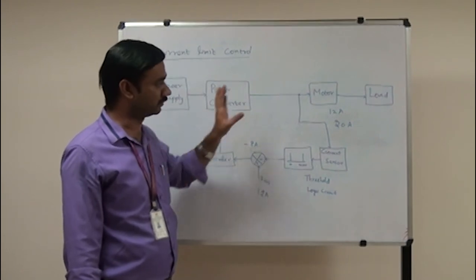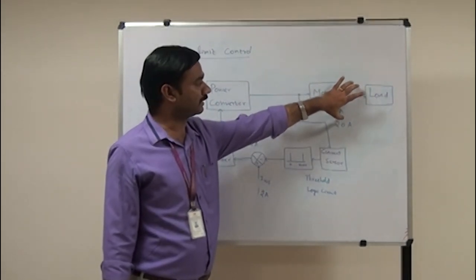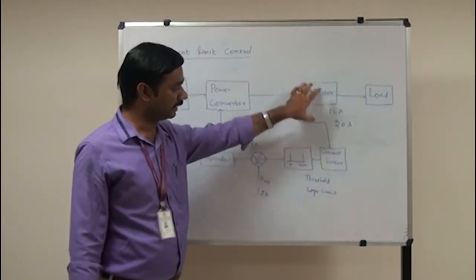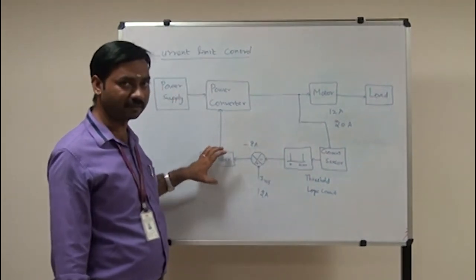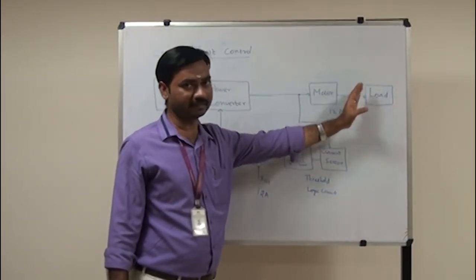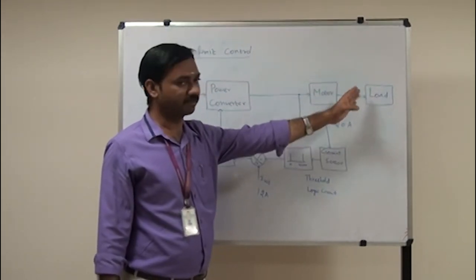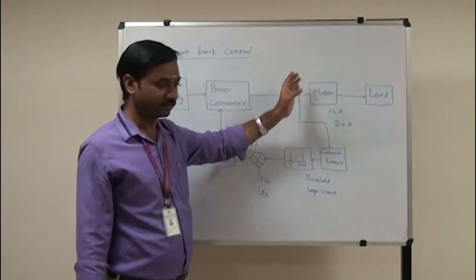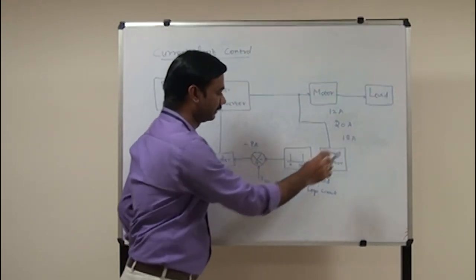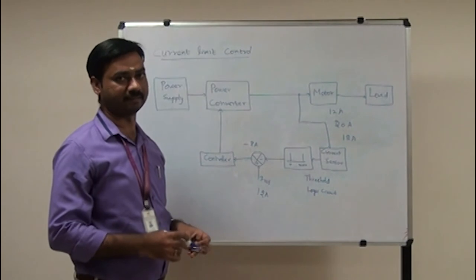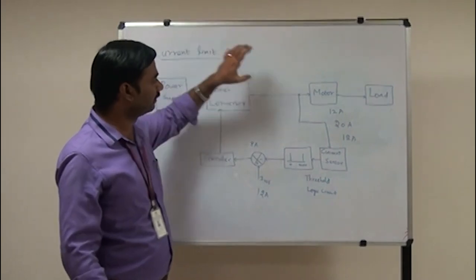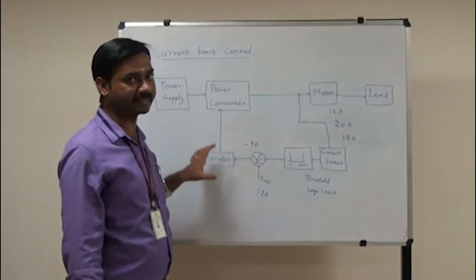This is the main purpose of the closed loop current limit control system — protection. When the motor is at risk of damage, the current sensor and comparator trigger the controller to turn off the power converter switches. Once the fault is cleared, the current returns to 12 amps and the motor resumes normal operation. This is how current limit control works: sense the current and maintain it at or below the maximum rated level.